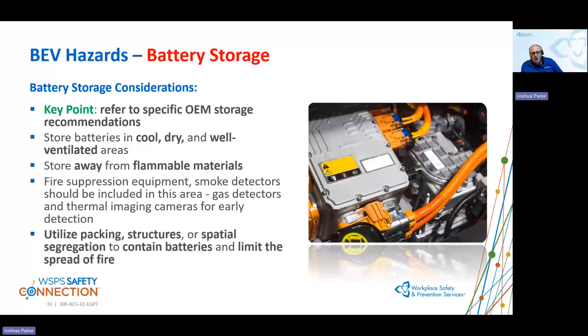We've talked about the fire suppression system, smoke detectors, these types of things to maybe monitor the area where you are storing these. Utilize packaging structures, spatial segregation to contain batteries and limit spread of fire. So what we mean by this is we've seen workplaces put in partitions, limiting how many batteries are stored in one area so that if there is a thermal event, they can contain it within zones. That's more or less what we're talking about here. Might be a challenge for different workplaces, but think about how we can use different areas of your workplace, even outside, following the manufacturer's requirements to help minimize worker exposure if there is a thermal event. Okay, moving forward here.